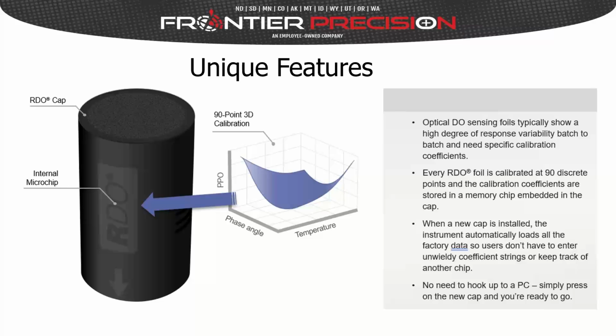So anytime you connect to this, you can see, okay, hey, I've got 380 days left on this cap before I need to replace it again. Now, when a cap expires, it'll still read dissolved oxygen. You just won't be able to calibrate the sensor with an expired cap on it.